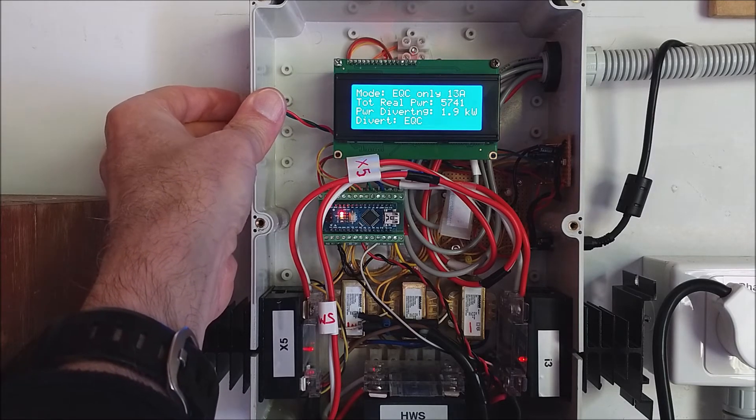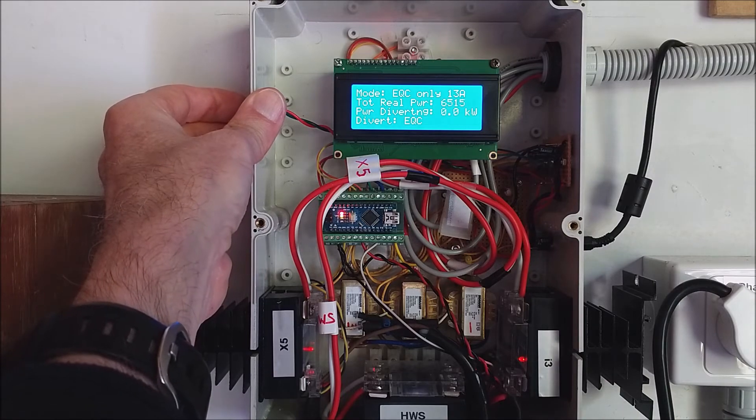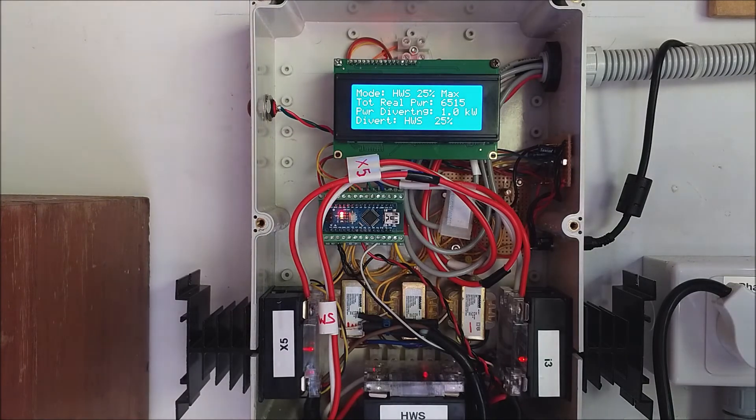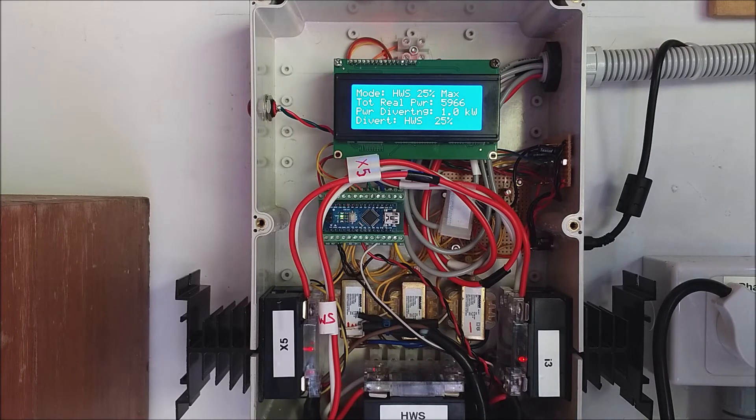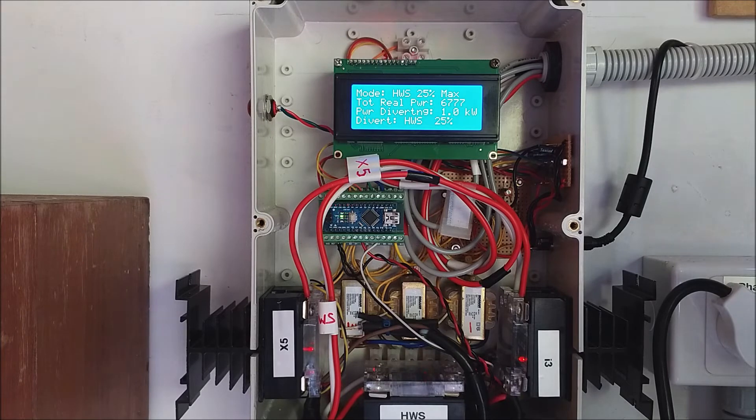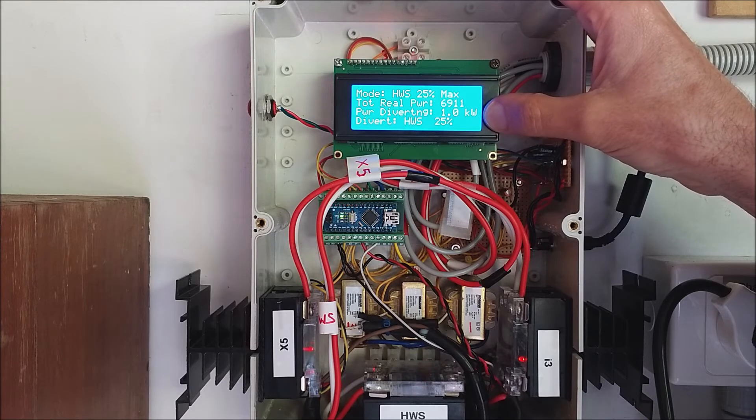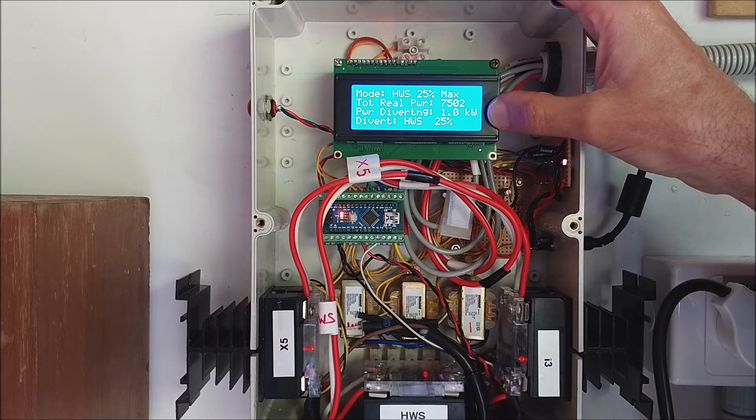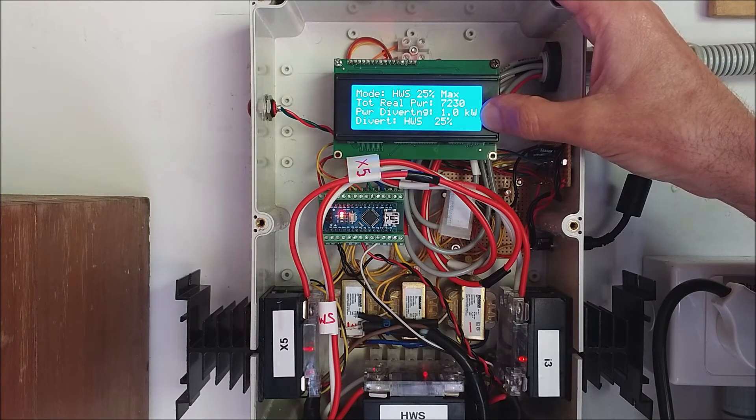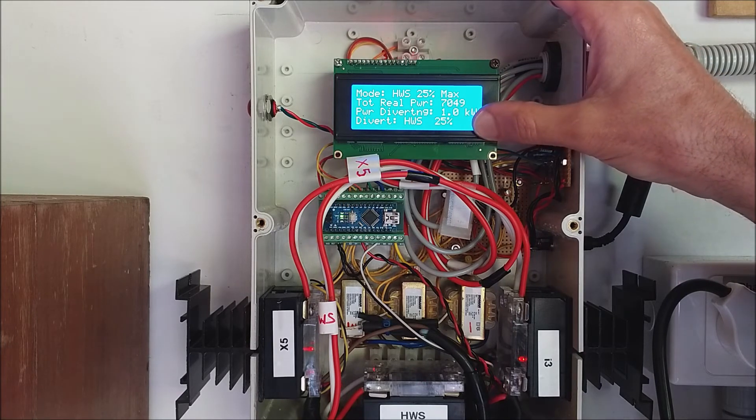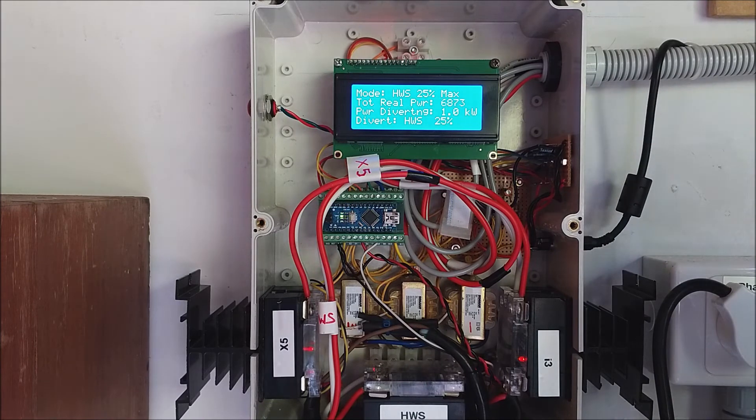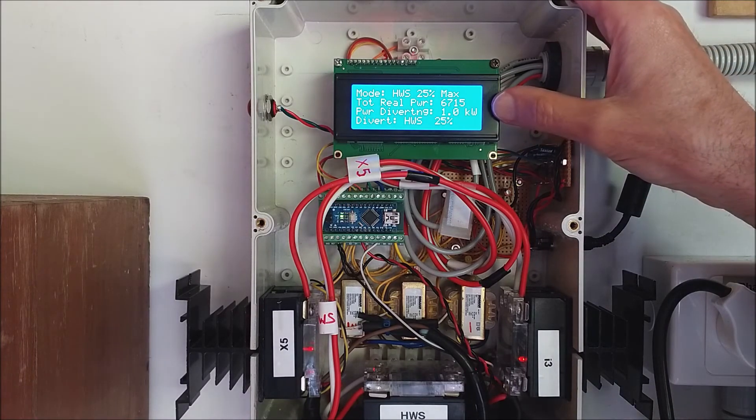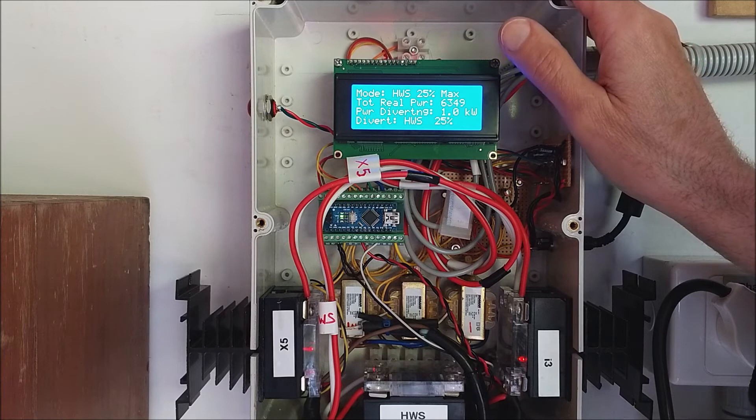Another mode here just to do with charging of our second EV at high levels, 8 amps 10 amps and 13 amps. And then we have these modes which is quite interesting, hot water service 25 percent max. So what that means is that we're applying a duty cycle a maximum duty cycle of 25 percent irrespective of our energy exports. So in this case we're exporting almost seven kilowatts but we're only diverting about a quarter of that 3.9 which is give or take one kilowatt hour to or one kilowatt to the hot water service. So essentially once we've exceeded that 25 percent maximum power, so you can work up to the 25 percent from that minimum cut in 50 or 100 watt cut in right up to one kilowatt hour. Once we've hit the one kilowatt threshold we will not export any more to the hot water service.